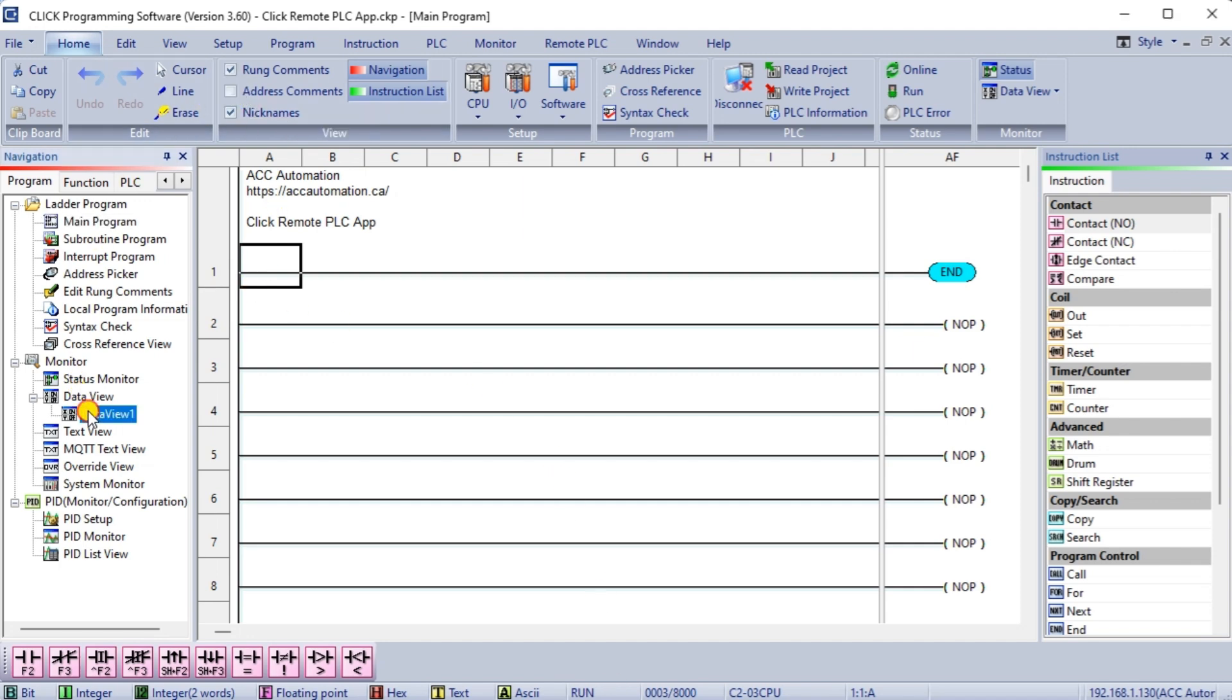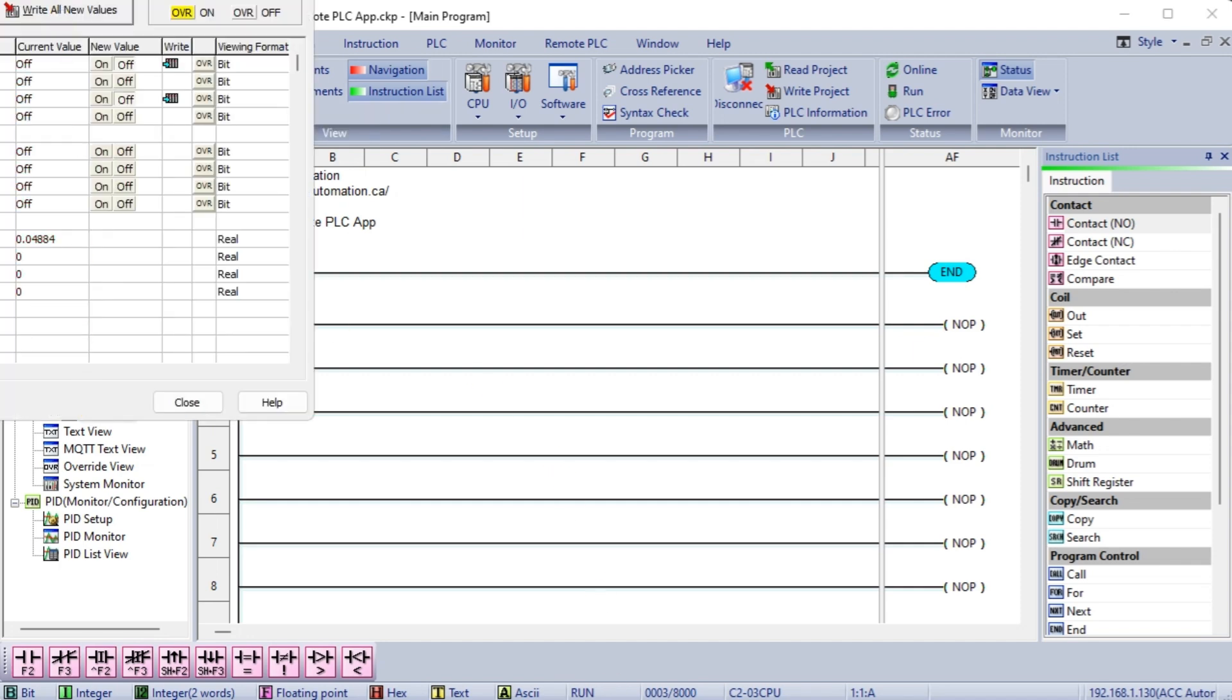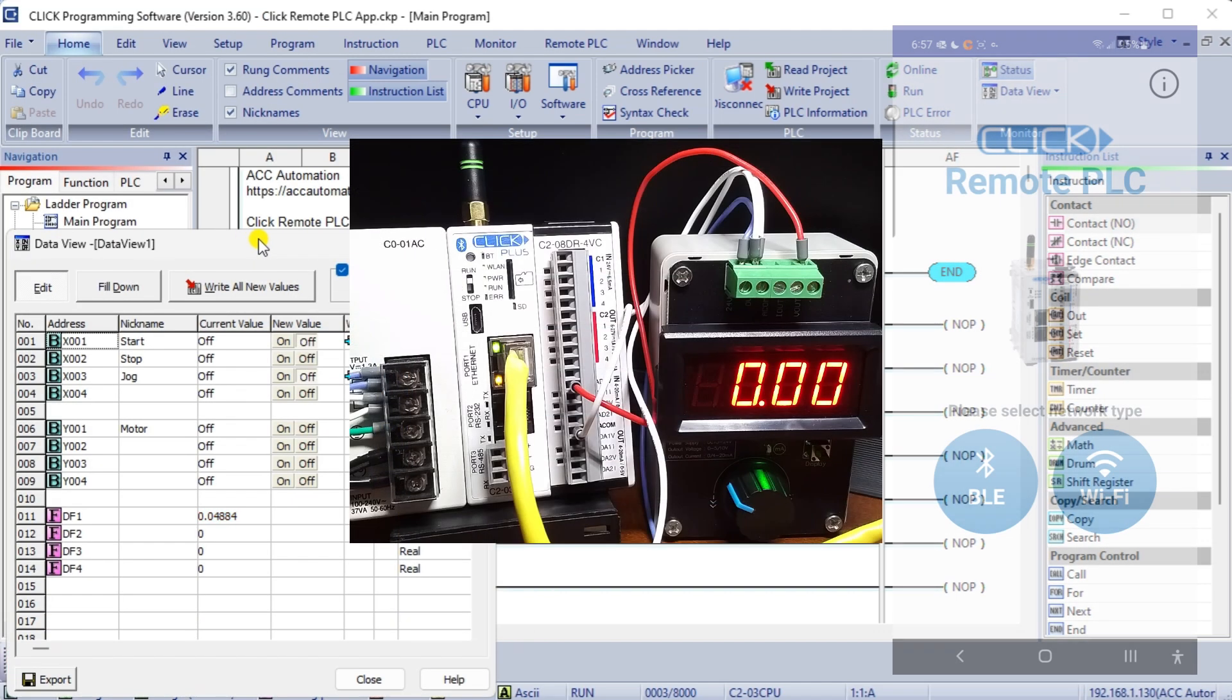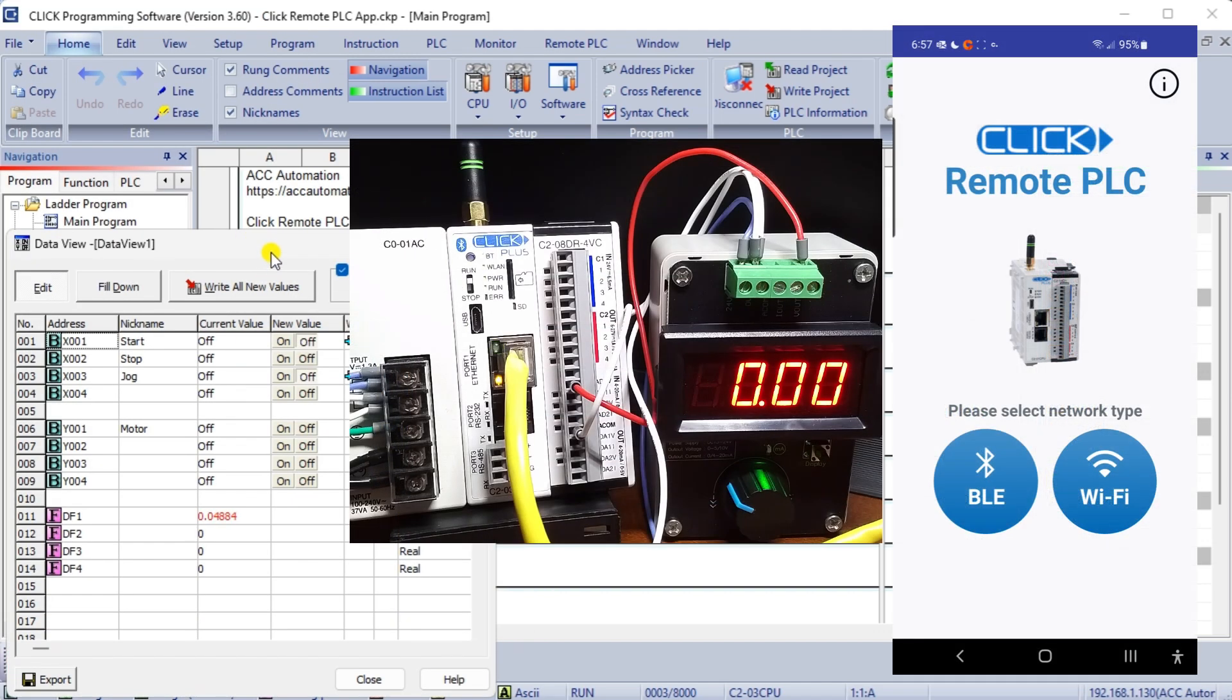Test and demonstrate click remote PLC app. Call up the data view window in the click programming software. This will allow us to monitor and change the I.O. we are monitoring. Note that since we do not have a program in the PLC to change the physical outputs, we can control these with the remote app or through the data view window. In an actual application, internal bits can be programmed in parallel in the ladder logic and controlled through the app.